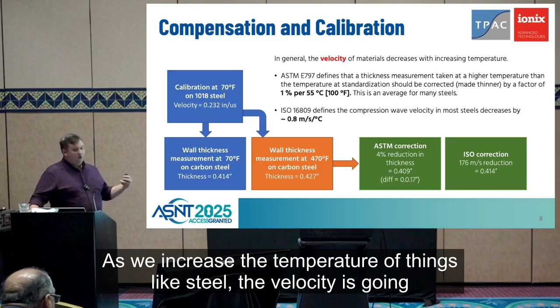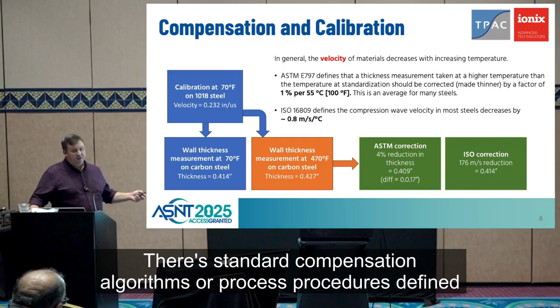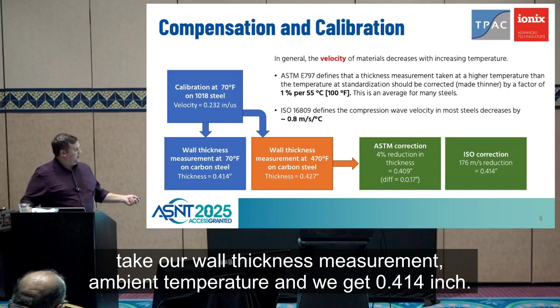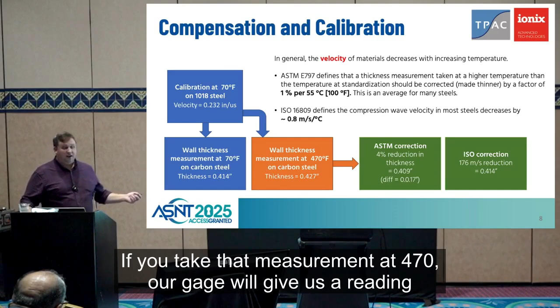As we increase the temperature of things like steel, the velocity is going to decrease, and we have to compensate for that. There's standard compensation algorithms or process procedures defined in ASTM E797 and the ISO standard. If we give that by example, take a piece of steel with a set velocity, take our wall thickness measurement at ambient temperature, and we get 0.414 inch. If you take that measurement at 470, our gauge will give us a reading of 0.427, so it's not correct.